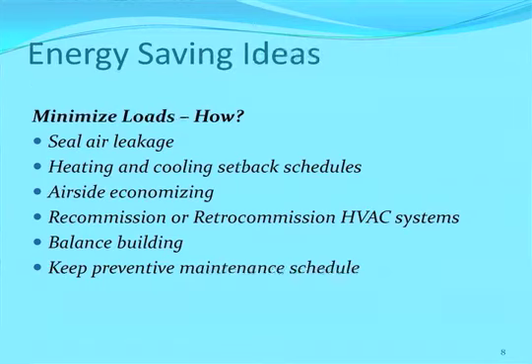Airside economizing is so good an idea, you're going to see it come back again when I talk about shifting loads. Recommissioning or retrocommissioning your HVAC systems, make sure that they're doing what you want them to do. Balancing the building. You don't want to be blowing the air outside, the conditioned air, outside of the zone that it's intended to be in. And then, last but far from least, is keeping a preventive maintenance schedule.